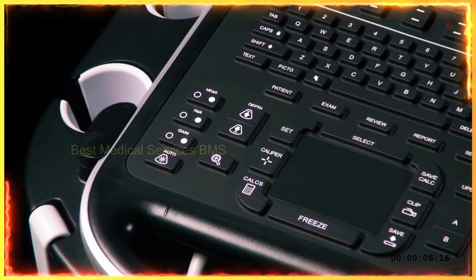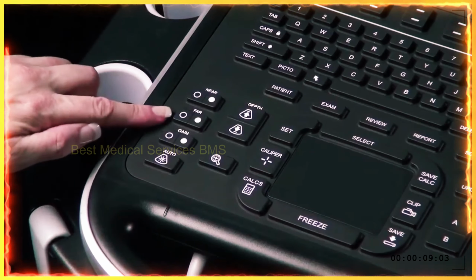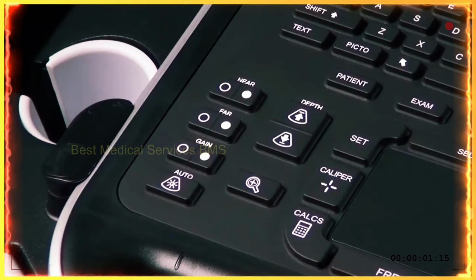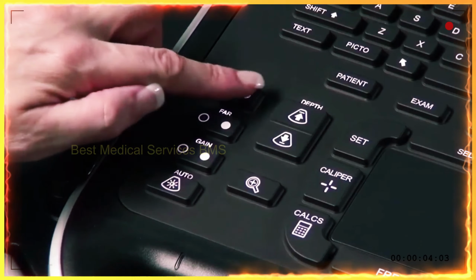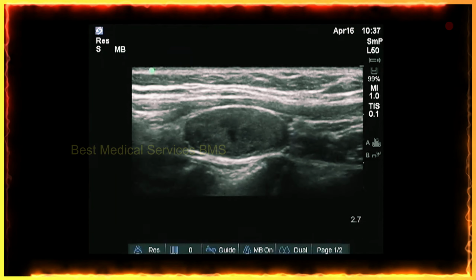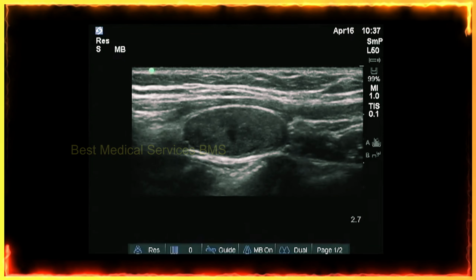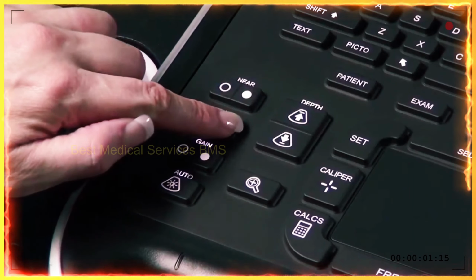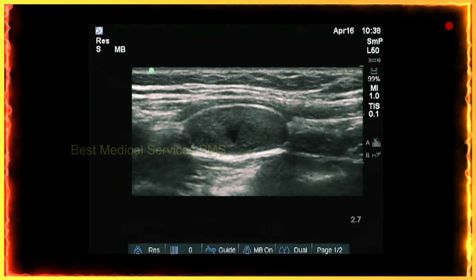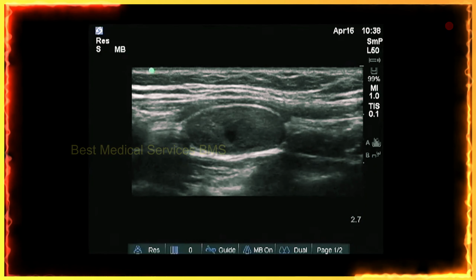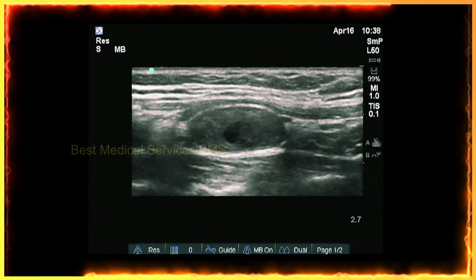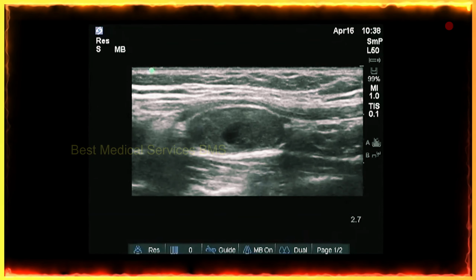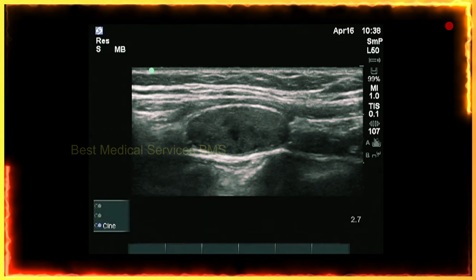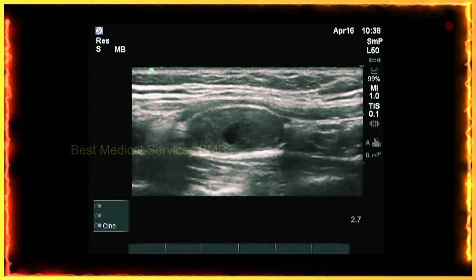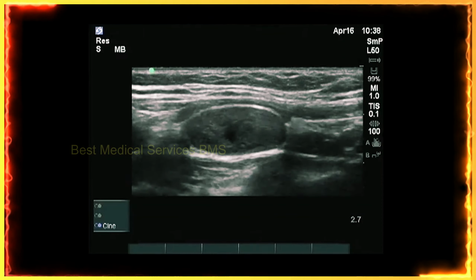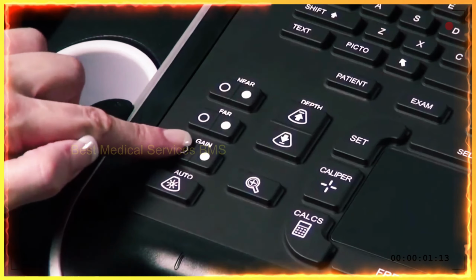On the left-hand side, there are 3 controls for gain compensation. Near adjusts the gain applied to the near field of the image. Far adjusts the gain applied to the far field of the image. And gain adjusts the overall gain applied to the entire image. When an image is frozen, the gain key can be used to review images in the Cine buffer. Increasing or decreasing the gain buttons scrolls backward and forward through the stored images.